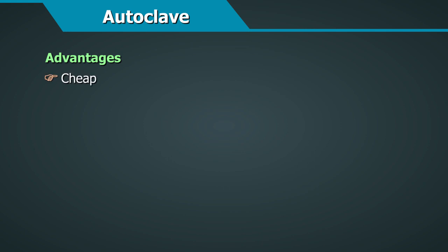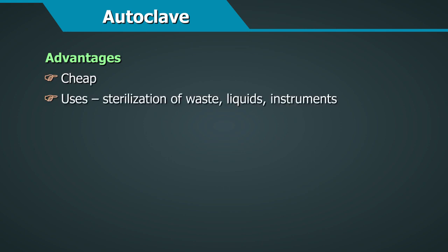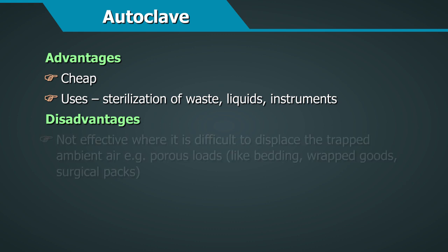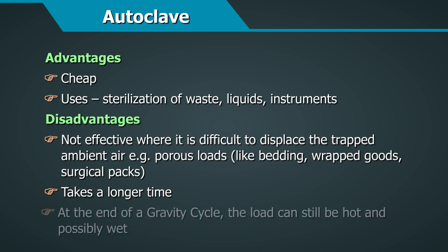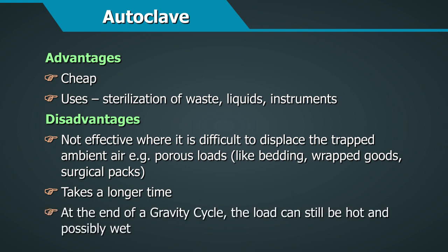The gravity displacement autoclave is a cheap method. However, it is not effective where it is difficult to displace trapped ambient air, for example with porous loads like bedding, wrapped goods, and surgical packs. It also takes a longer time, and at the end of a gravity cycle the load can still be hot and possibly wet.